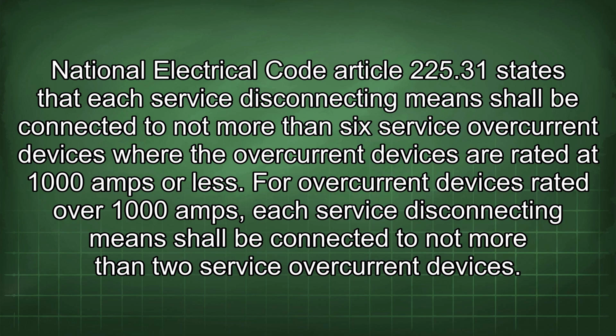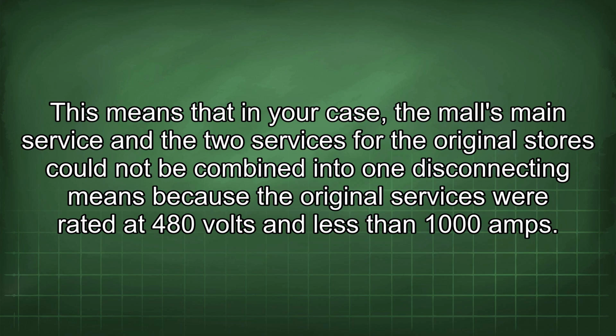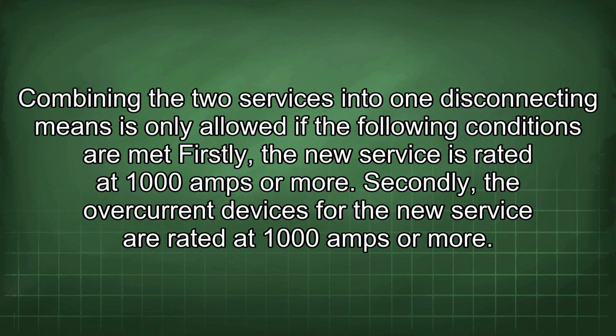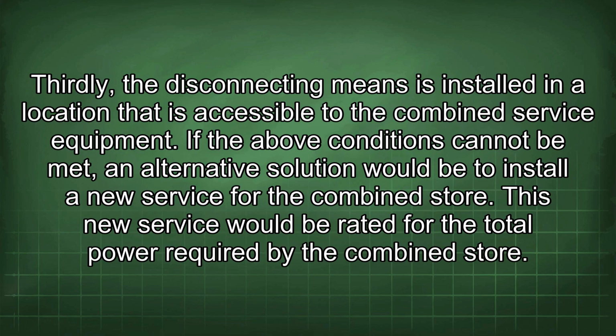This means that in your case, the mall's main service and the 2 services for the original stores could not be combined into one disconnecting means because the original services were rated at 480 volts and less than 1000 amps. Combining the 2 services into one disconnecting means is only allowed if the following conditions are met. Firstly, the new service is rated at 1000 amps or more. Secondly, the overcurrent devices for the new service are rated at 1000 amps or more. Thirdly, the disconnecting means is installed in a location that is accessible to the combined service equipment.